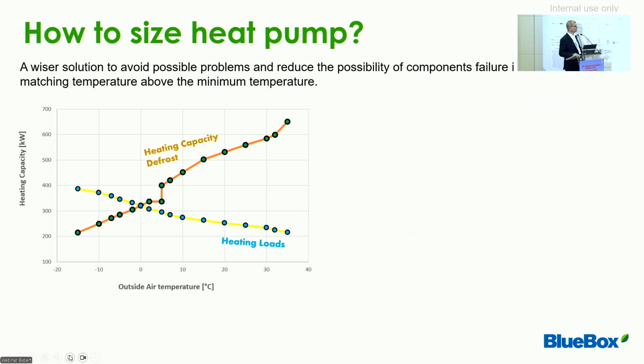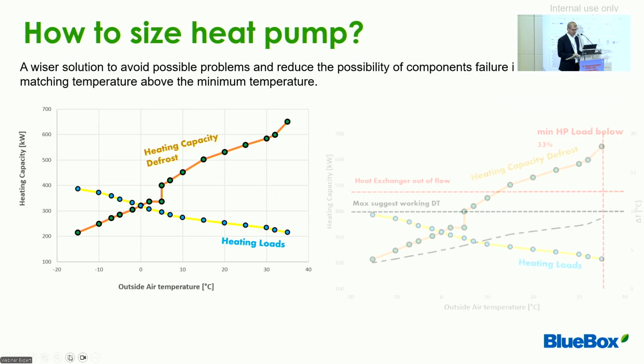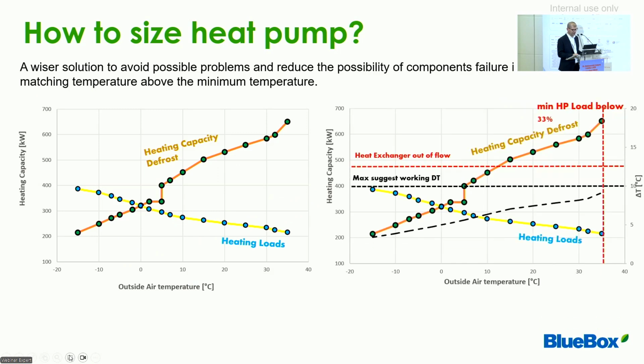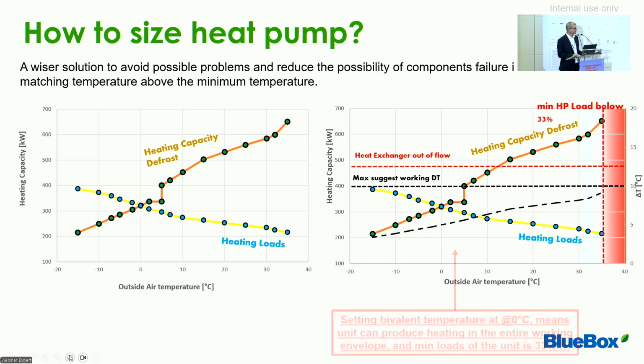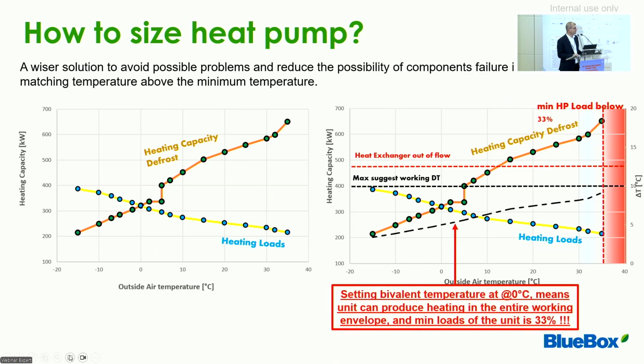will be to size heat pumps with an intermediate bivalent temperature that will allow the heat pump to work in the entire working envelope with a minimum load of 33% at higher ambient temperatures. This is very important, and we think it's a typical mistake, meaning selecting the heat pump in the worst possible conditions.